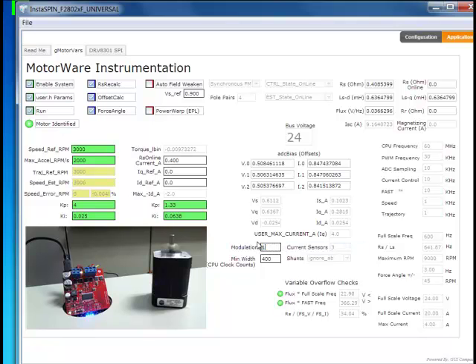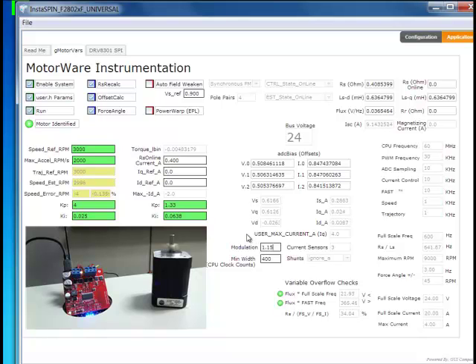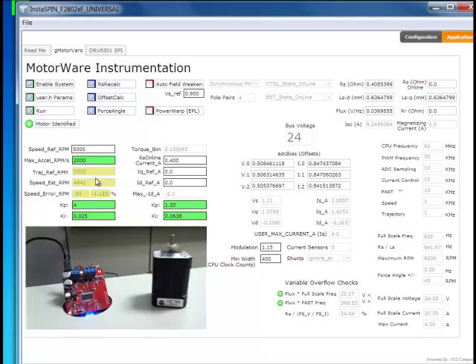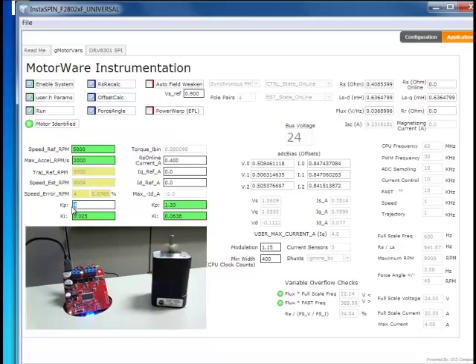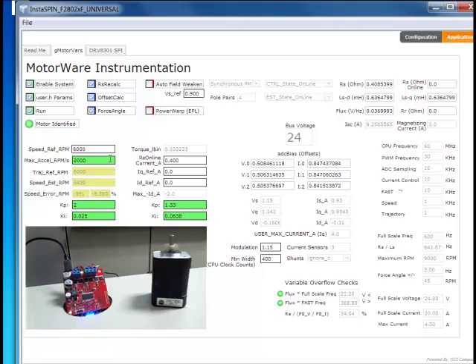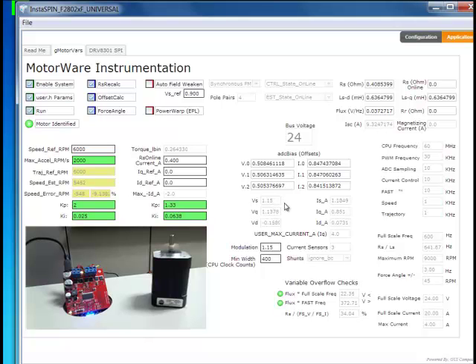Let's try the SVPWM. This has a modulation index of 1.15. We're going to allow another 15% essentially of voltage across. Let's see how fast we can run now. Let's again try the 5,000. We're able to hit that and we're actually oscillating a little bit. Our speed controller is probably a little too tight. We'll go ahead and tune that a little bit. Let's see if we can go faster. Let's try 6,000. You'll see with this modulation, we went up to a value of a full 1.15 allowed, which is giving us about 5,400 RPMs.